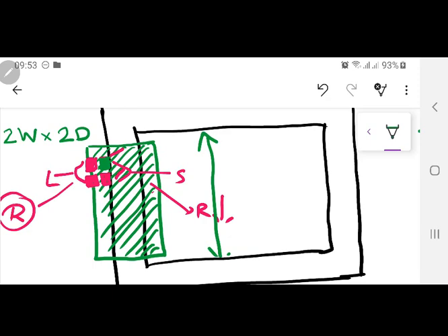This is actually the width here. So this is the 2W, and 2 depth means this is the depth here. So there are 2 conductors in the depth direction. This is one disposition, one way of arranging the conductors. Whenever a low voltage winding is designed, you have to tell how your conductors are arranged. It can't be just 2 cross 2; it can be 1 cross 4 also.